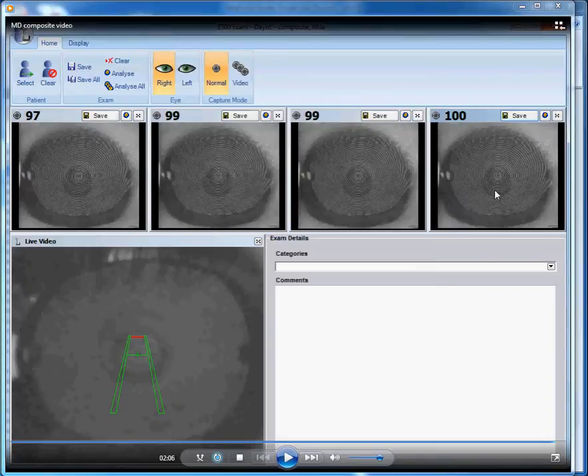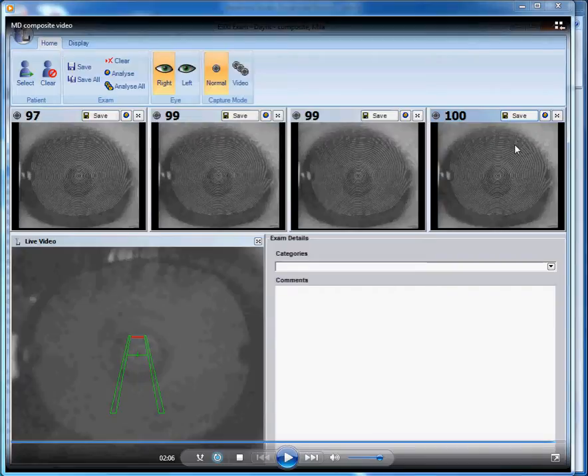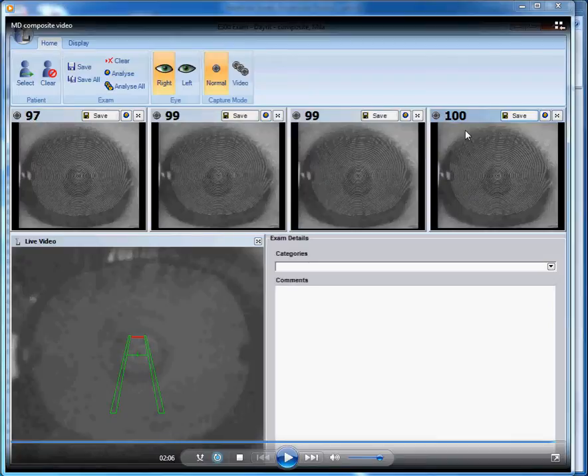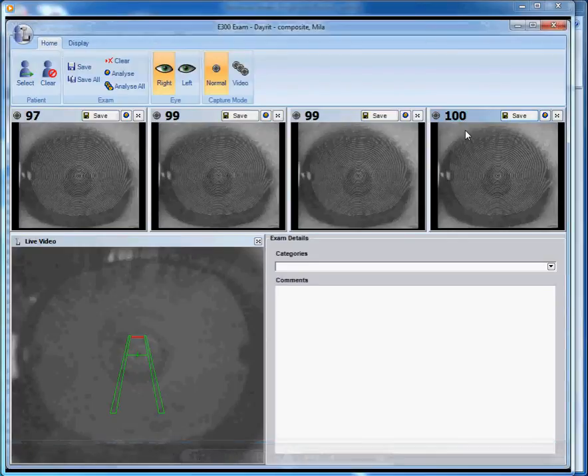In this case, we're able to push the placido reflection to the superior cornea. You see some eyelash shadows here. Possibly we could do a better job of pulling the eyelid back and pulling those eyelash shadows away from the placido reflection.